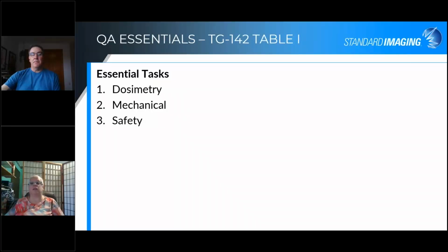So Hugh, can you tell us a bit more about the essential tasks? Yeah, I mentioned our Table 1, which covers the morning dosimetry check, the LINAC output, things like that, and some of the mechanical checks and the safety.